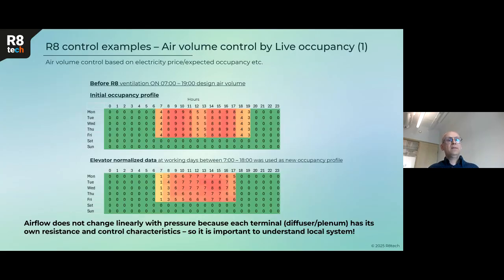Real example about the occupancy. As I said, usually the buildings are working on static conditions, with ventilation in static condition. My background is also HVAC, and I definitely know that with VAV dampers, the airflow does not change linearly with the pressure, because each terminal has its own resistance and control characteristics. So it's very important to understand the local system and how it works. But before, usually they work static and on timing, sometimes with full speed and half speed options available.